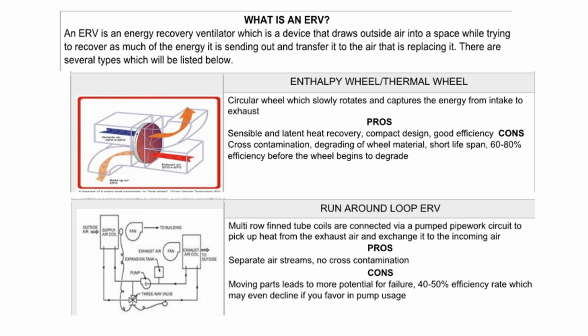So there are several types. There's the wheel, the thermal enthalpy wheel, which slowly rotates and captures energy from intake and exhaust. It does sensible and latent heat recovery, and it's a very compact design with good efficiency. The cons are you're cross-contaminating the air and degrading the wheel material, which gives it a relatively short life span. Also, as the wheel material degrades, your efficiency does as well. So 60 to 80% efficiency is the best case scenario on that style.